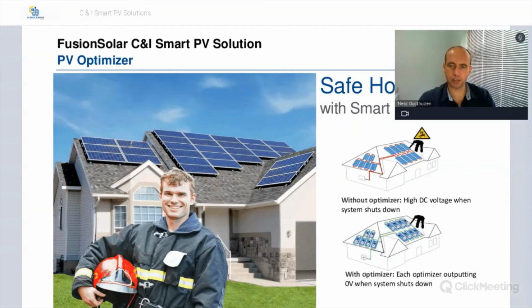But if you're using the Huawei optimizers, you can actually make full use of the available roof area and then just have better performance. So in this table below, you can actually see that if you look at a common module without an optimizer, your system capacity would have only been 13.7 kilowatts if you only used one segment or two segments of the roof. But using the optimized solution, you can go up to 24 kilowatts, which gives you an additional 10.7 kilowatt. The actual yield from the system, if you have no optimizers, would have been 14.768 kilowatt hours per year. Fully optimized, you can go to about 26.51. So you've got a lot better yields when using the optimizer if it's specifically a complex installation, as this roof is with different angles and directions that the roof is facing.